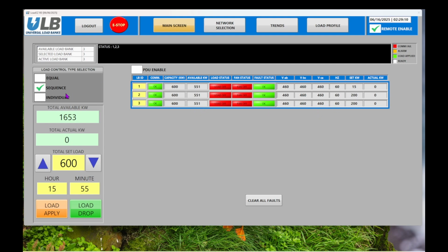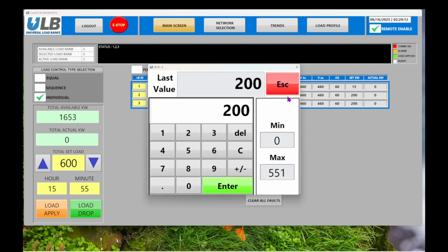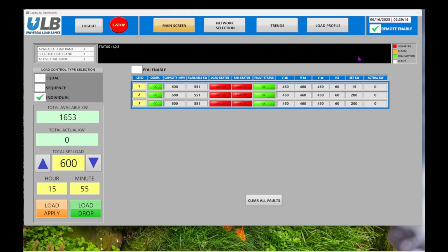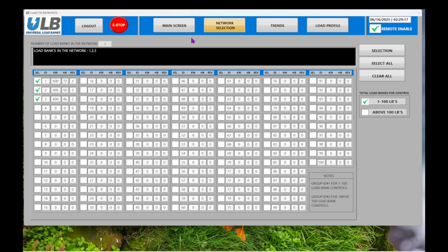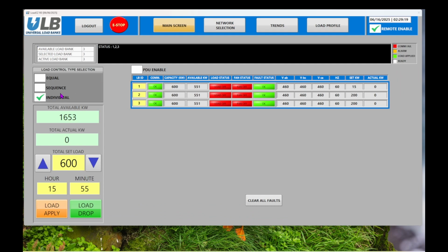Let's now control the load banks. First, select Remote Enable, choose the number of load banks to operate. Select the control mode: equal, sequence, or individual. Set the desired load duration in hours and minutes. Press Load Apply to apply the load, press Load Drop to remove it. In this demo, let's select equal, and now press Load Apply. If needed, pressing E-Stop will immediately shut off both the load and fans across all active load banks.